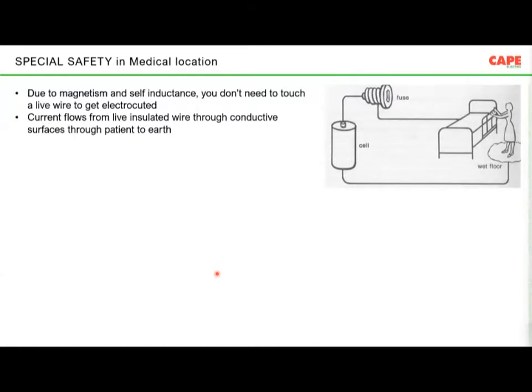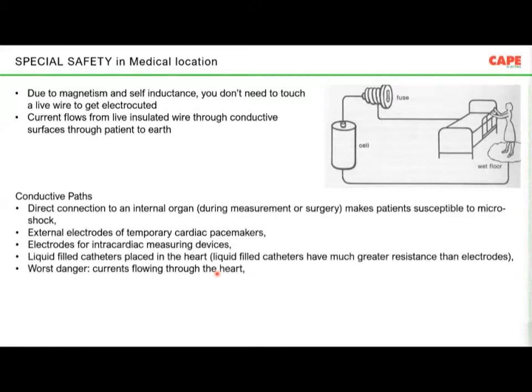So sometimes you don't need to touch an equipment to get a shock. Current flowing through the insulation itself sometimes creates a shock hazard. And a lot of conductive parts exist, and probably they are also connected to the human, like a direct connection to an internal organ during measurement or a surgery, then external electrodes for temporary cardiac pacemakers, electrodes for intracardiac measures, then liquid-filled catheters.